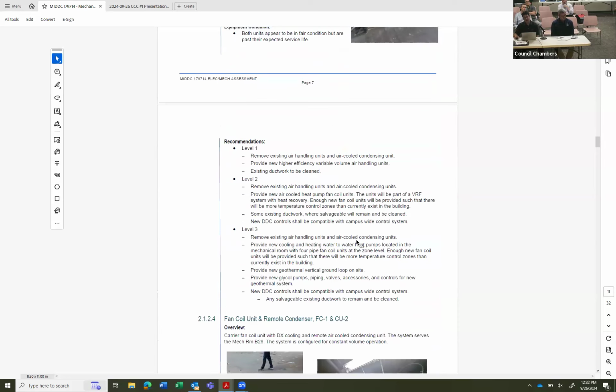And regarding the levels as they apply to the air handling units, essentially level 1 would be remove the existing air handling units and air cooled condensing units and replace with new ones that will be more efficient and provide new high efficiency variable volume VAV boxes as needed too, and I'll get into that in the next section. And the level 2 recommendation also includes complete removal of these air handlers and replaced with smaller, more modular zone level fan coils for the VRF heat pump system.